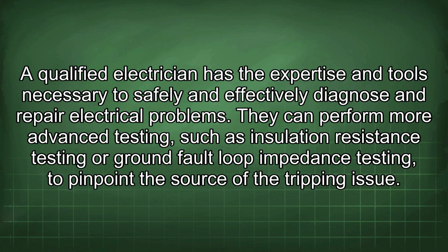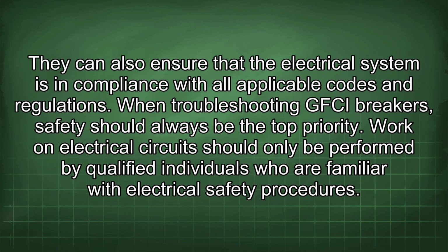They can perform more advanced testing, such as insulation resistance testing or ground fault loop impedance testing, to pinpoint the source of the tripping issue. They can also ensure that the electrical system is in compliance with all applicable codes and regulations. When troubleshooting GFCI breakers, safety should always be the top priority. Work on electrical circuits should only be performed by qualified individuals who are familiar with electrical safety procedures.